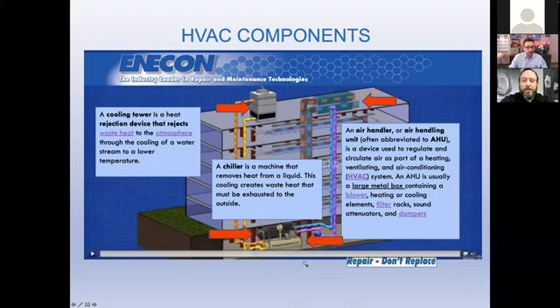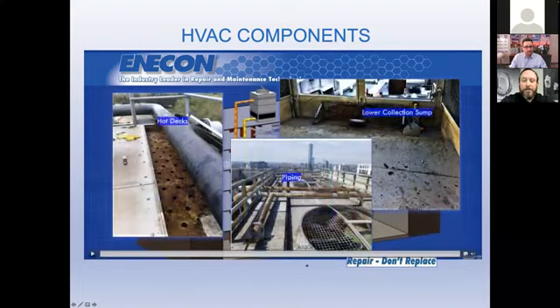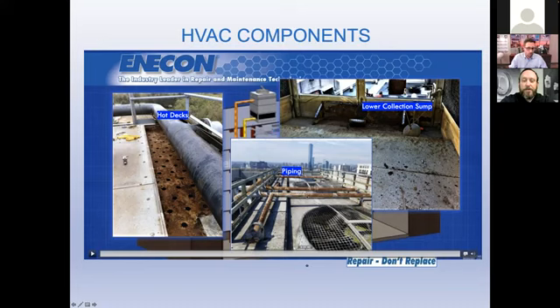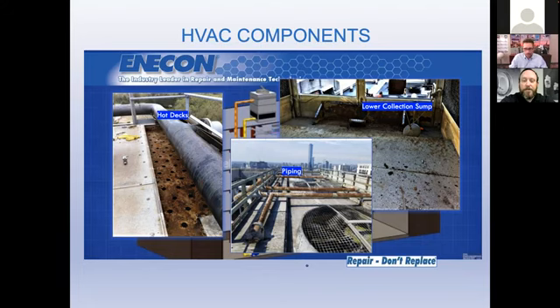The last in the line of the three primary components is the cooling tower. The cooling tower is a heat rejection device that takes the warm water and rejects it out into the atmosphere, and that completes the HVAC system in a building. Cooling towers specifically have a lot of different types of corrosion issues. You have the water coming into the cooling tower from the top, which we call the hot decks. The water then matriculates down through the cooling tower into the lower collection sump, which creates another set of corrosion issues. Also, the cooling tower piping not only is subjected to the mist from the cooling towers, which can cause corrosion over years, but also to evaporation and environmental corrosion as well.